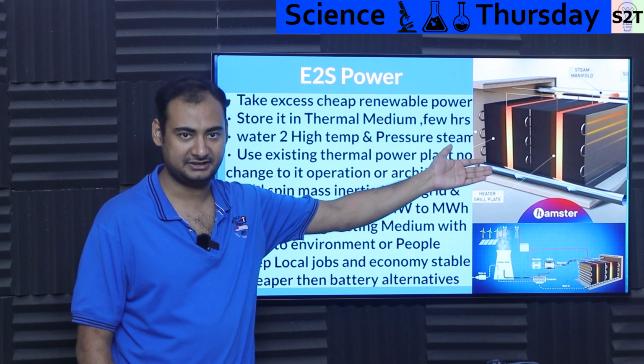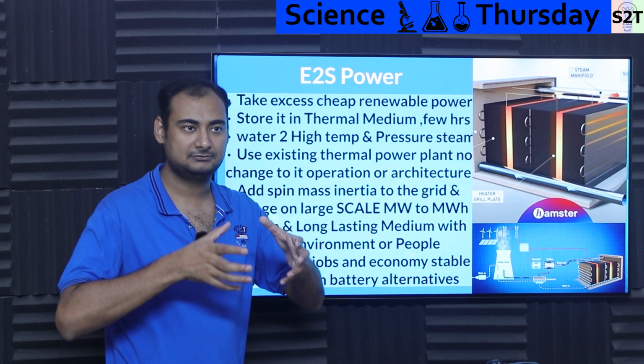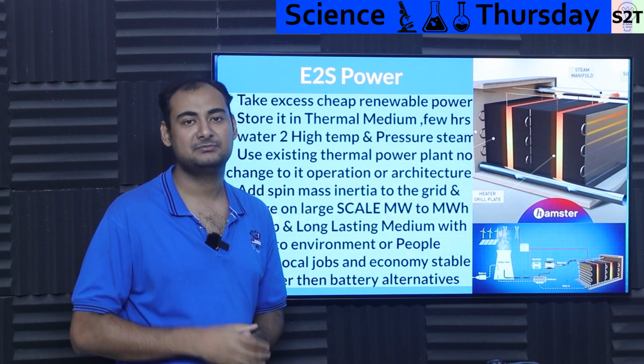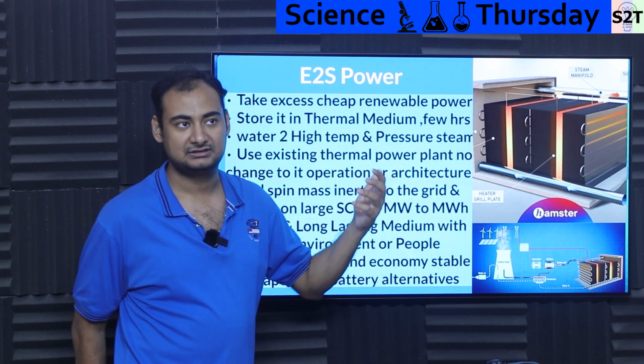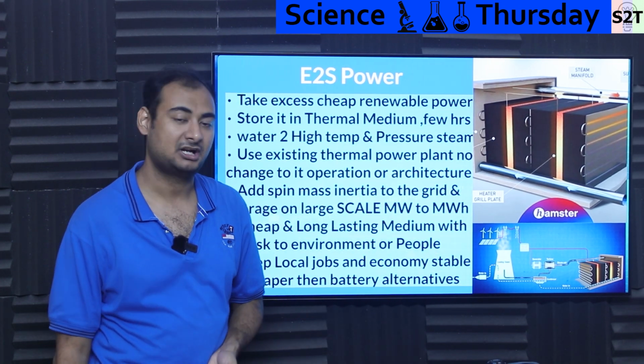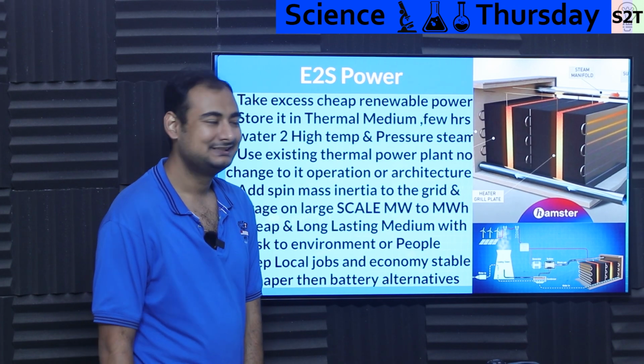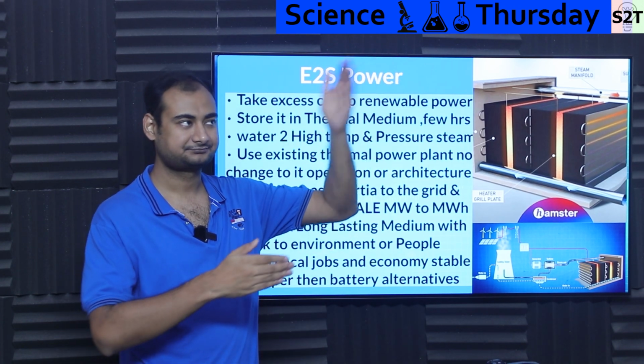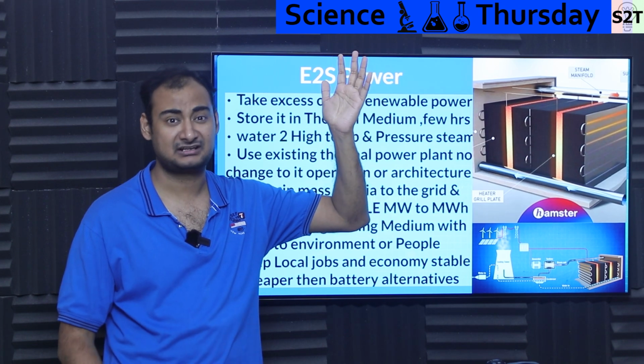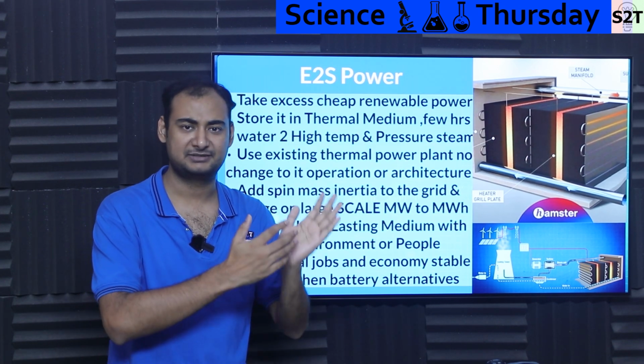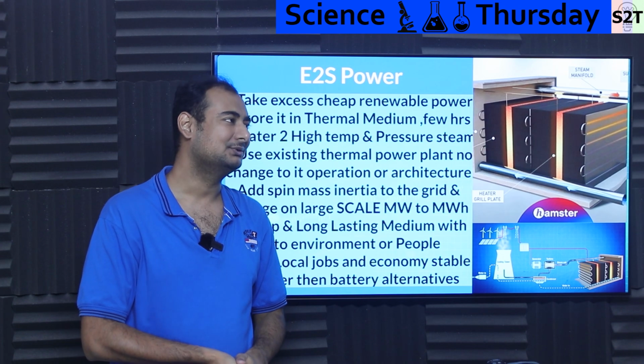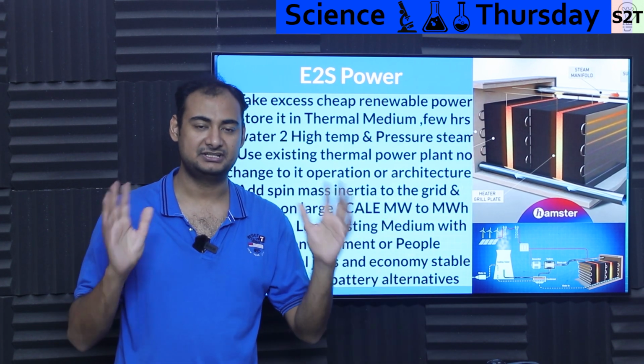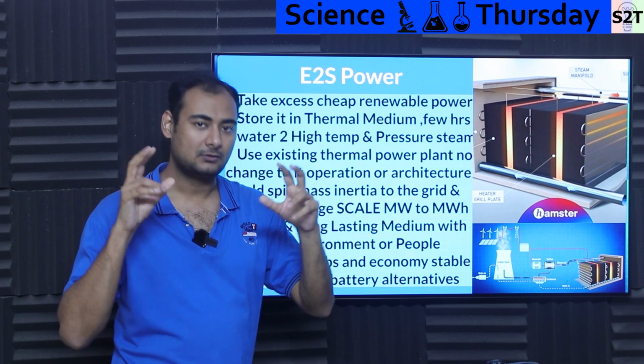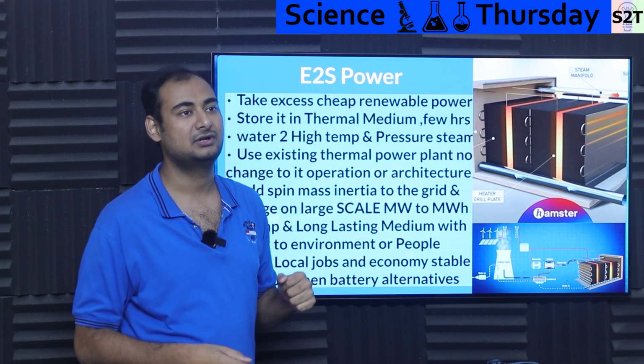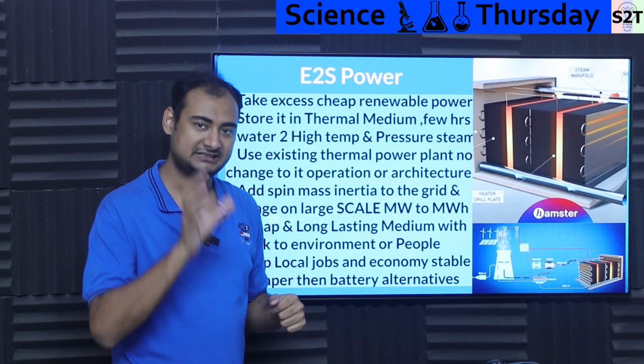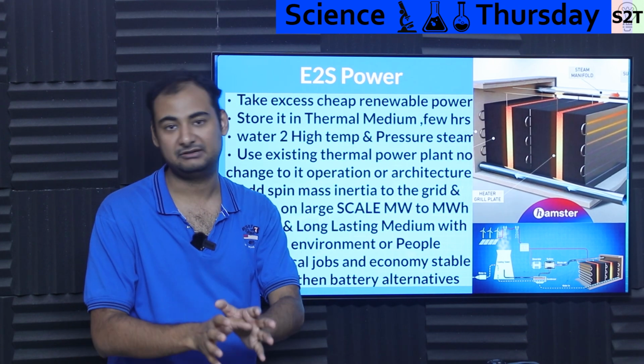How big can these things get? They can start with basically the power output, meaning how much oomph it can dump, directly limited by the substation. If the power plant was designed for, say, 1 gigawatt output, that's the maximum you can do. Sometimes you may have a high voltage transmission line with spare capacity, so you can upgrade the transformer and get more out of it, but generally you won't. So whatever the coal power plant's rating was, say 50 megawatt, 100 megawatt, 12 megawatt, whatever it is, that becomes your power limit.